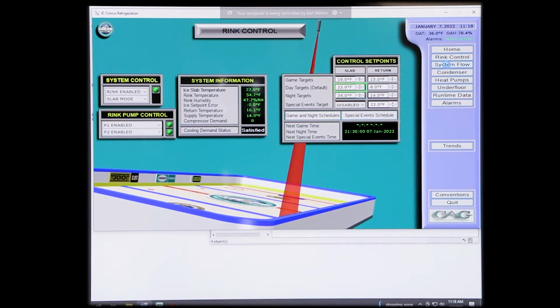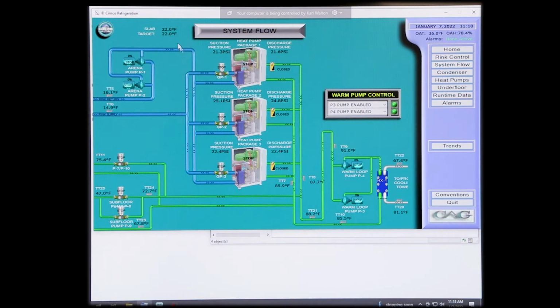Okay, system flow. Upper left corner, your current slab reading, your current slab target. So as we discussed before, we will fire at 22.5 degrees based on that, and you'll run down to 21.5 and then shut off. P1, P2, again, you'll see the VFD speed references here in black above it. You'll always see those at 100%. You have your supply temperature, return temperatures here. In the middle, you have your suction pressures of the freon of each one of the heat pumps. They go to 21 when the system shuts off because the compressor equalizes. Totally normal.